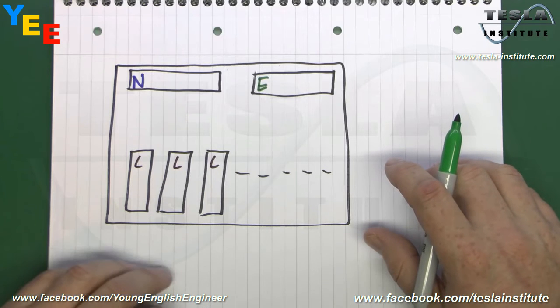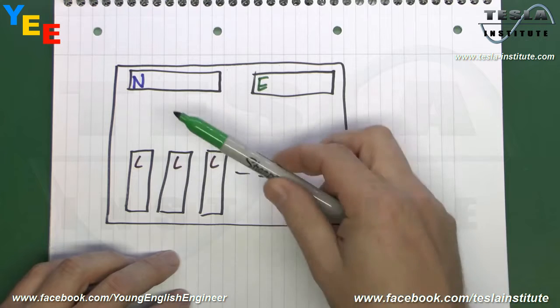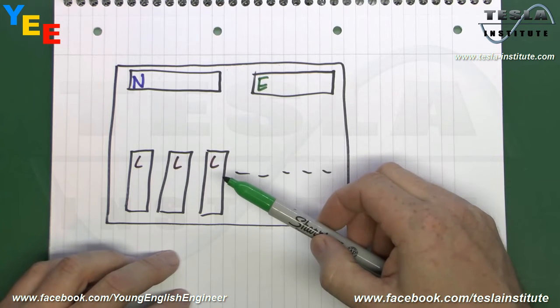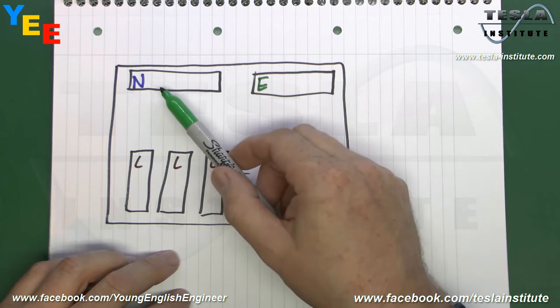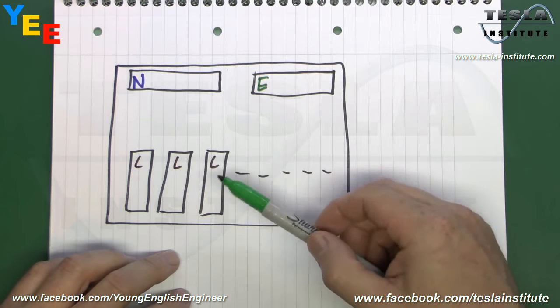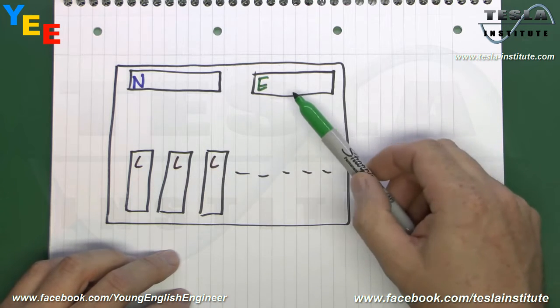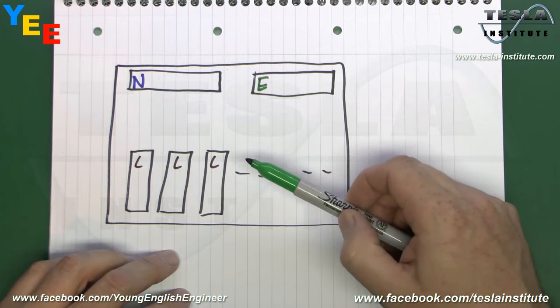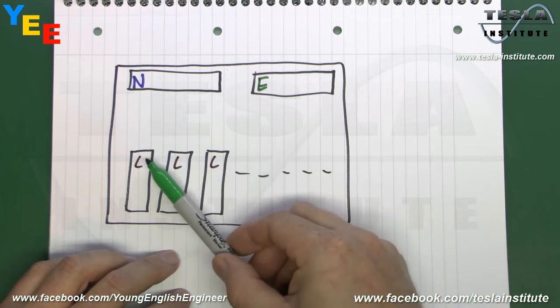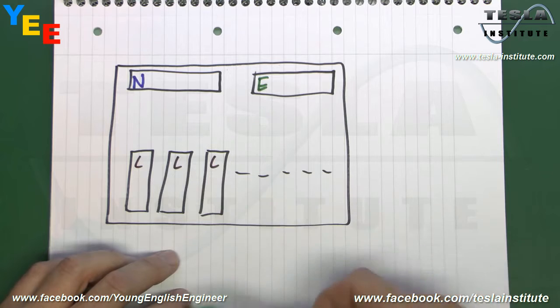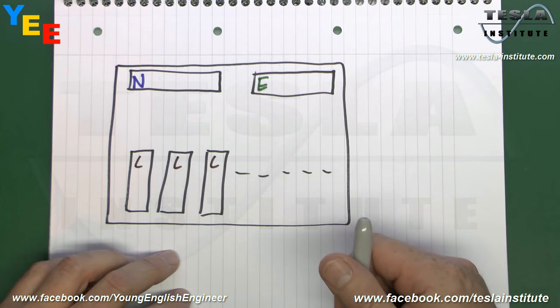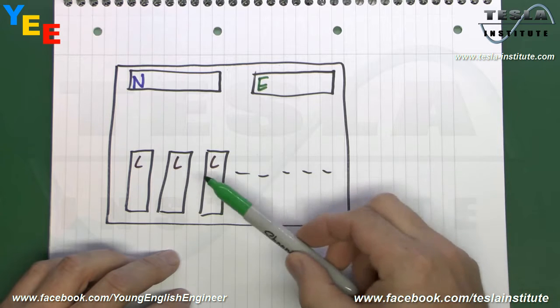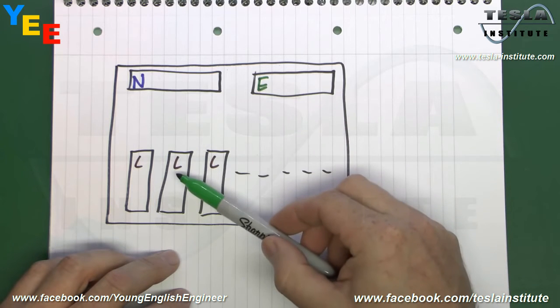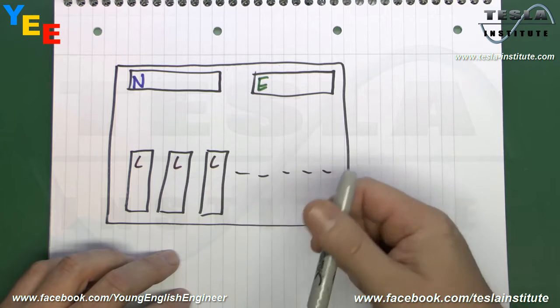Now, in a typical installation you have some kind of consumer unit or fuse box or something similar. And inside there you're going to have the 3 wires coming in, so the neutral is going to the typically neutral bar at the top, the earth or protective conductor is going to an earth bar there, and then your lines will connect to the fuse or circuit breaker or whatever you have in the particular device. And to do the insulation resistance testing, it's necessary to disconnect the neutral and line conductors from these 2 locations.